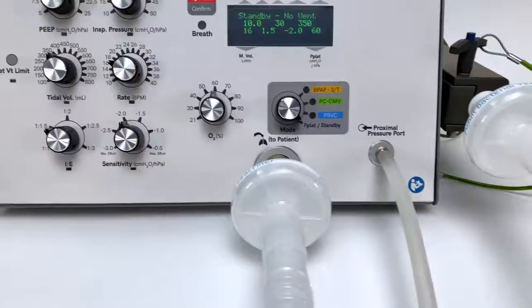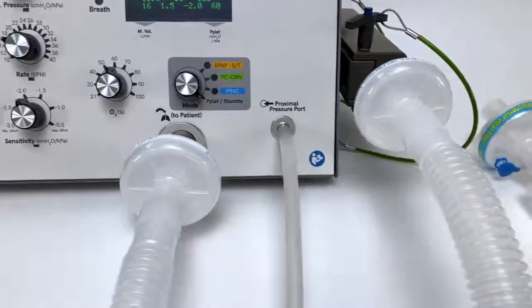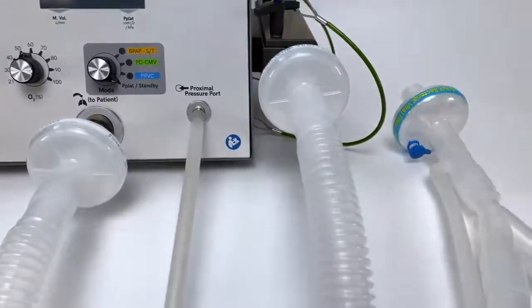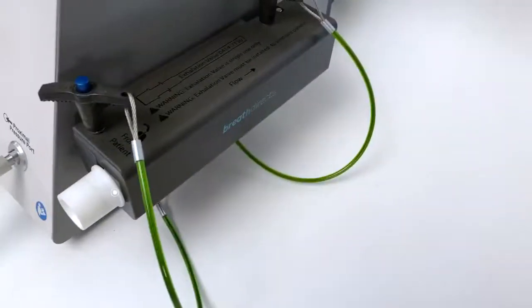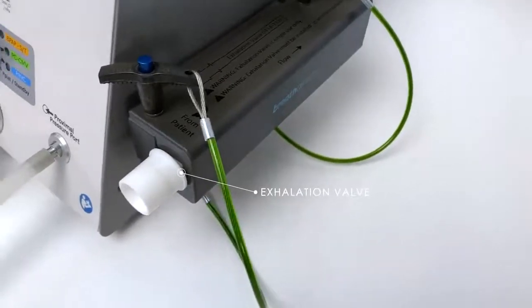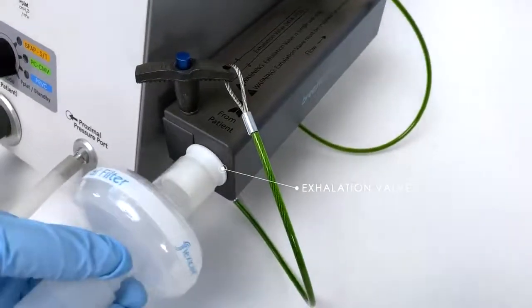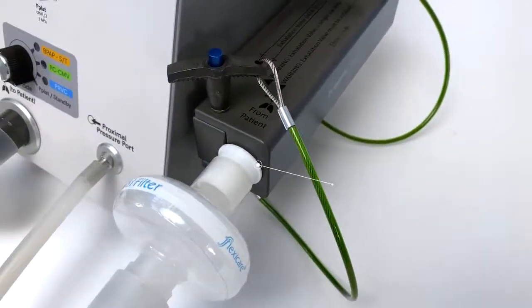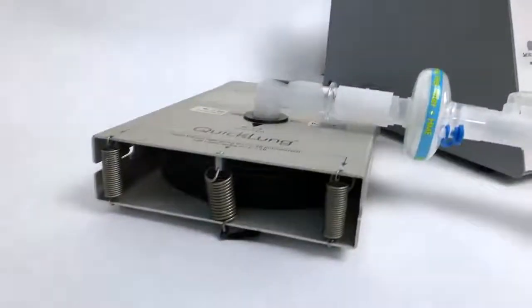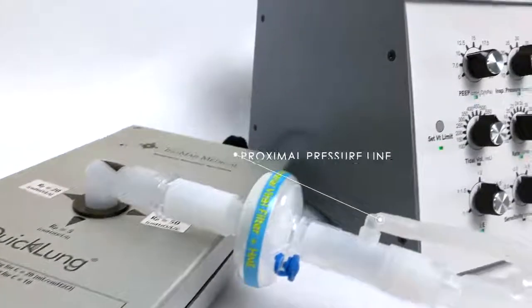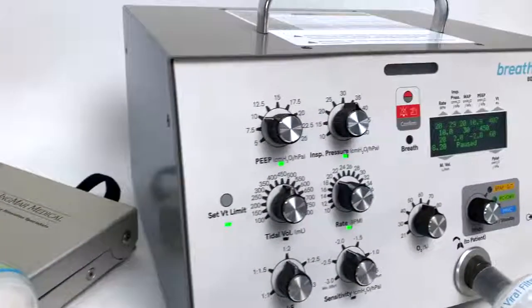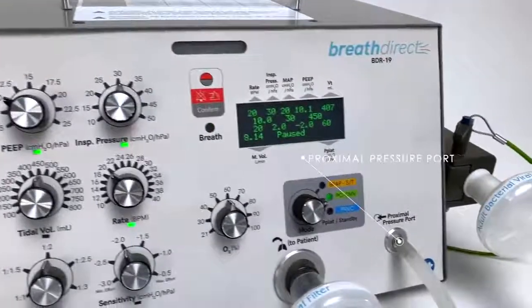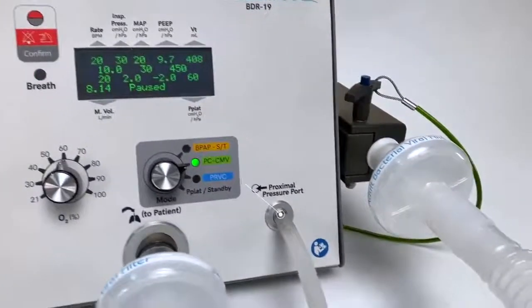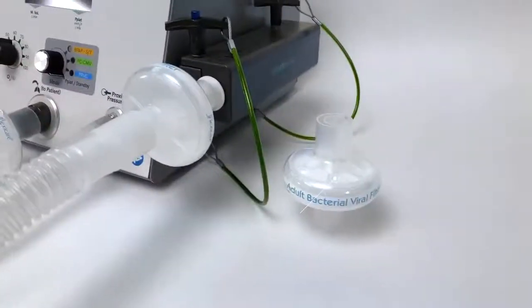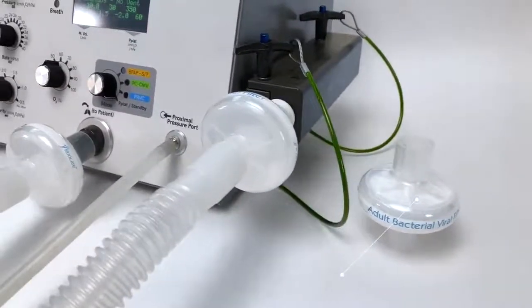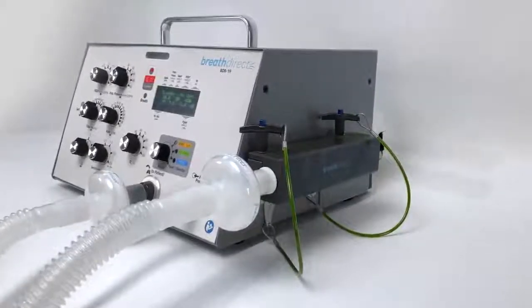The BDR-19 uses commonly available universal dual-limb patient circuits. A proprietary circuit is not required. The expiratory limb attaches to a built-in exhalation valve, which accurately and reliably helps regulate pressure throughout the breathing cycle and controls the PEEP pressure during the expiratory phase. Pressure at the patient Y is constantly monitored through the proximal pressure line attached to the proximal pressure port on the front of the ventilator. A slight purge flow keeps the proximal pressure line free of water. All connections are compatible with standard bacteria filters, and the exhalation valve is easily replaceable after each patient.